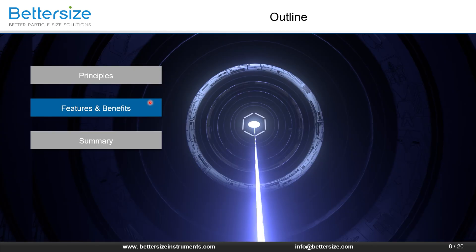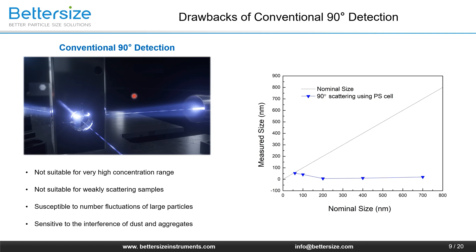After understanding the principles, let's move on to the features and benefits. There are some drawbacks of the conventional 90-degree optics. For example, the 90-degree optics is not suitable for high concentration range, nor for weakly scattering samples. In addition, this optics is susceptible to number fluctuations of large particles and also sensitive to the interference of dust and aggregates within the samples. When measuring a size standard sample at its original concentration, the 90-degree optics cannot provide a value close to the certified value, suggesting its limited concentration range.